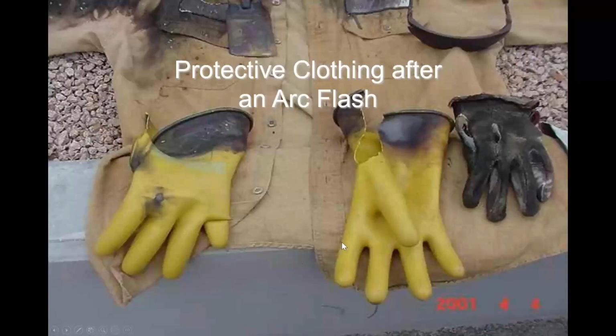So this is PPE. This is showing how rubber gloves with the leather protectors hold up. Outside, these have to be longer than the leather, so you can see how much damage to the rubber in themselves. They're not going to provide protection. This is not from the outside. This is from the inside. This is what ionization does in an arc flash. So it'll heat metal just like throwing keys in a microwave oven.